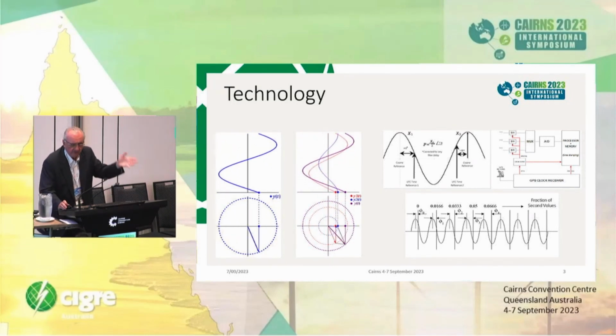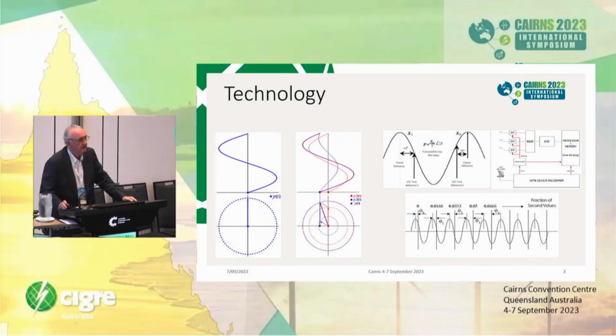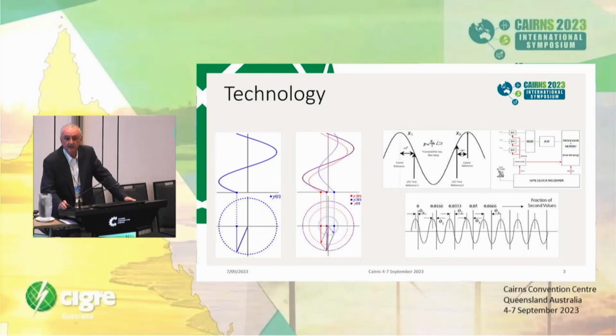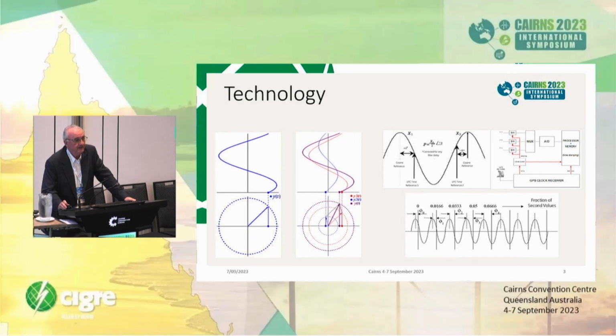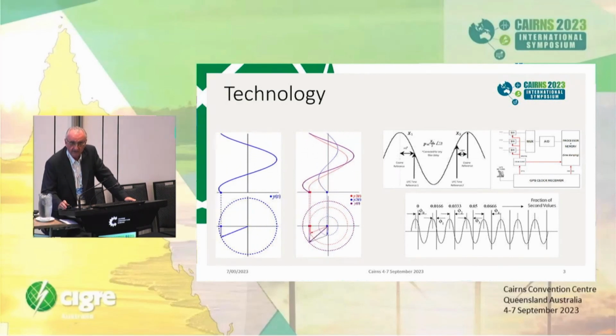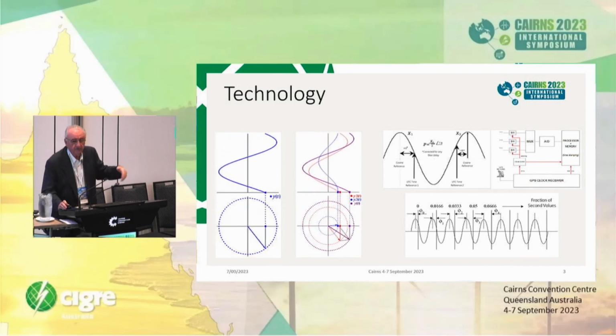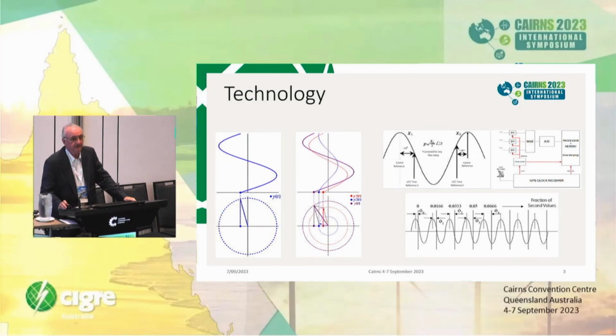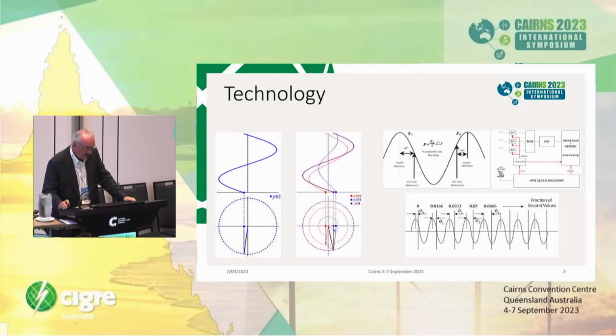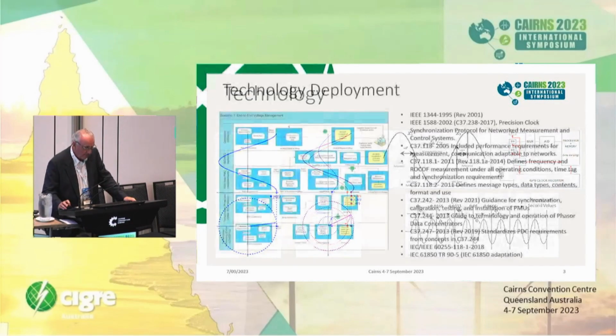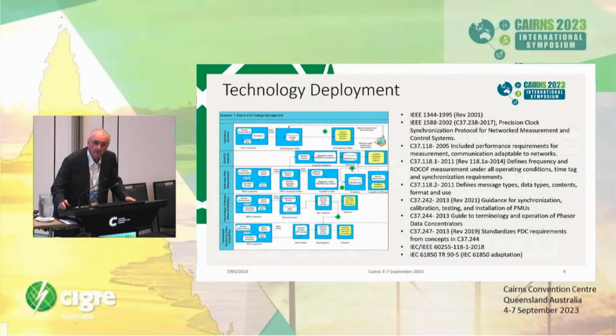A lot of people confuse this because the title of the PMUs is confusing. PMUs are not phasor measurement units. They are phasor calculation units. They calculate from samples and they report at a certain rate, whether it's 60 times, 120 times, or whatever per second.